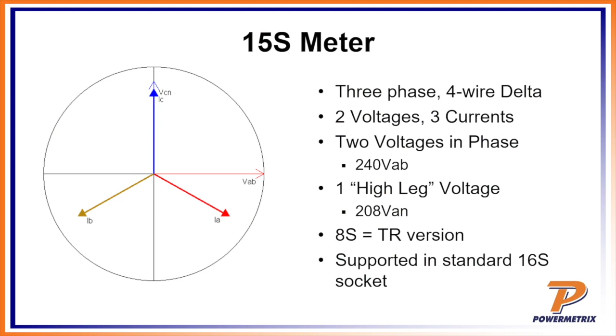Let's talk about the difference between a 16S and a 16K, or K-base. On the left is the 16S meter, and what does the S stand for? Socket type. So you use a meter socket, you can pull it in and out. On this one we have a lever bar that, once you open it, the jaws open, and I can easily remove the meter, insert it back, close the jaws, and it's got a tight seal.